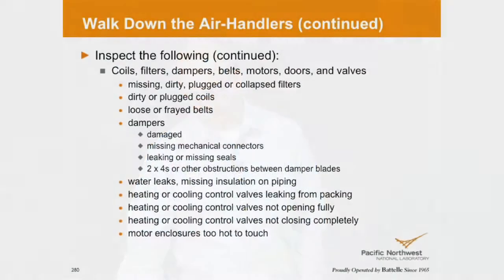So my only comment to that would be just periodically check them and keep an eye on them. Mine's still working, I'm gonna get rid of it. Depending on the type of fan system, some people, from what I've read, have said that you might create some added turbulence because those vanes do some air straightening on the fan if it's a dual inlet. But anyway, just things to be aware of. If you can get rid of them, by all means, I would say get rid of them. Add a VFD, and you will save energy with inlet vanes, but not nearly as much as with a VFD. There's a study done by a couple of guys, I could show you.